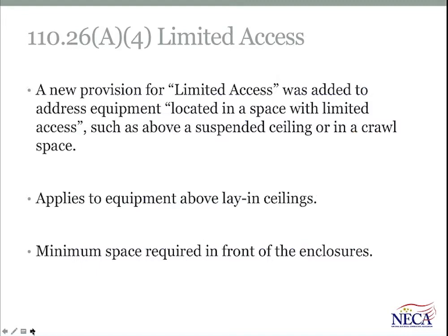Section 110.26 is all about providing workers minimum amounts of working space about equipment. And 110.26(A) sees a new list item 4 titled Limited Access added to address areas above a suspended ceiling or in a crawl space where the equipment installed in those locations would be likely to require servicing while energized. So this new list item 4 has the specific criteria that must be applied relative to the minimum amounts of working space in those areas. And this actually entered the code last cycle in section 424.66 for duct strip heaters. That was a change in the '14 code.